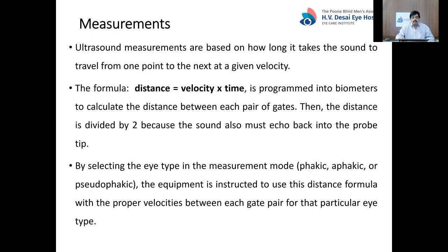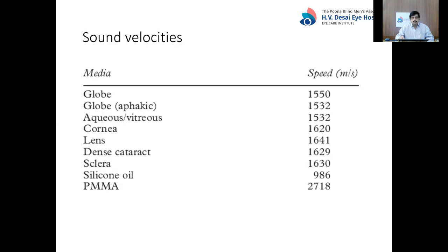By selecting the eye type in the measurement mode — whether phakic, aphakic, or pseudophakic — the equipment is instructed to use the distance formula with the proper velocities between the gate pairs for that particular eye type. For aqueous and vitreous, the velocity is 1532 meters per second, so in an aphakic globe, which is essentially all aqueous and vitreous, that speed is used.